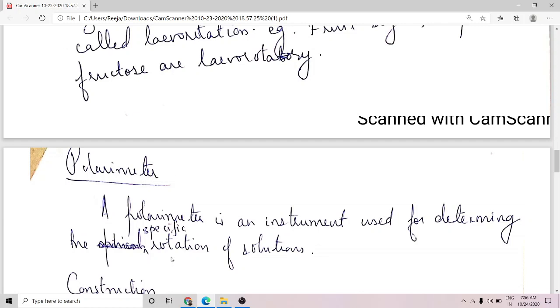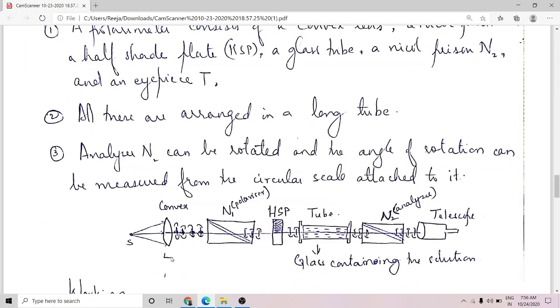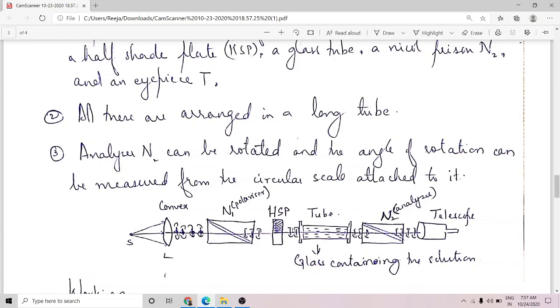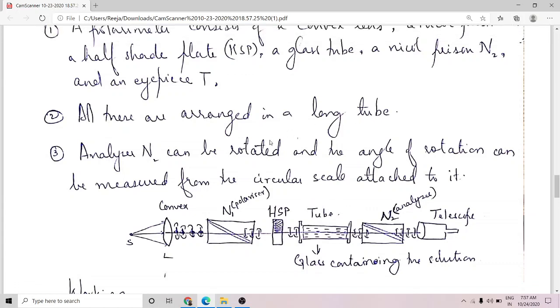The polarimeter, as shown in the figure, consists of a convex lens, a Nicol prism which is the polarizer, a Laurent half-shade plate — one half made of quartz and the other half made of glass — a glass tube containing the optically active solution, a rotating analyzer N2, and a telescope to view the observations. All these are arranged in a long tube. The analyzer N2 can be rotated and the angle of rotation can be measured using a circular scale attached to it.